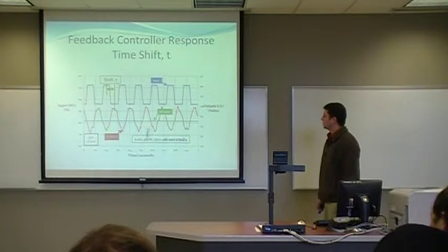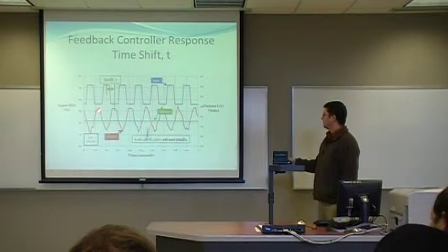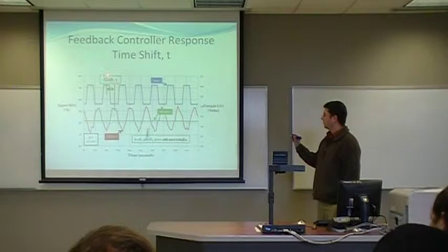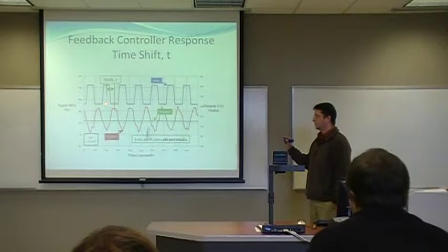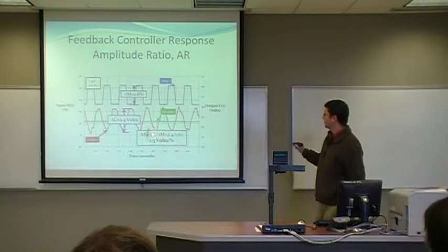So here's some results that we are, that actual diagram, the data that we took from the system. What we did was we plotted it on the timescale here, so we calculate the shift. And the shift is found between the midpoint of the input and the midpoint of the output. This came out to be, in this particular case, 0.06 seconds. It's also interesting to note that the peak of this is actually in between the peak, or rather the peak of the valley here. So this actually does correspond to the ultimate frequency, which we'll see in another slide.